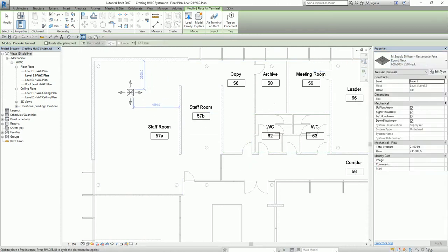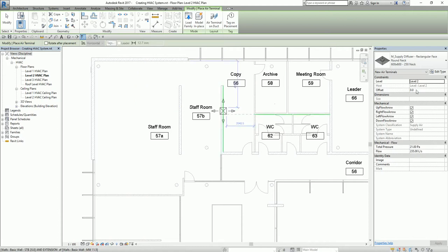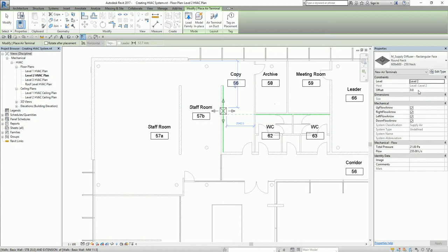If you're going to use the default family in Revit, like the air terminals, make sure you specify the offset distance, because by default the height of the air terminal is zero. So I'm going to key in 2400.